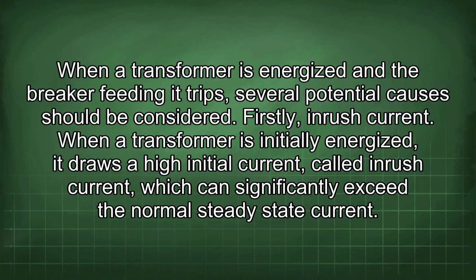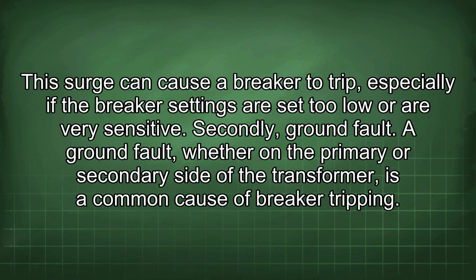When a transformer is energized and the breaker feeding it trips, several potential causes should be considered. Firstly, inrush current. When a transformer is initially energized, it draws a high initial current called inrush current, which can significantly exceed the normal steady-state current.